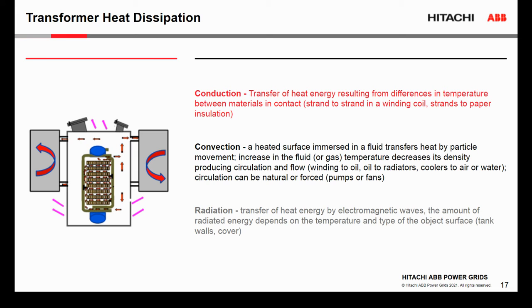Convection. So with convection, when we have the heat source as a winding, the heat from the winding increases the temperature of the surrounding oil. And with the higher temperature of oil, the density of oil goes down. And this creates natural circulation in the transformer tank.